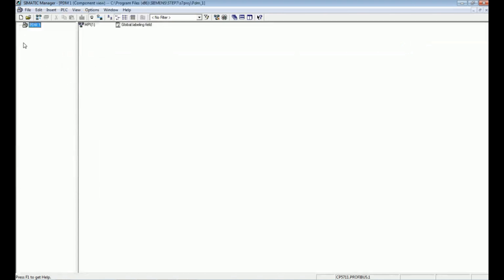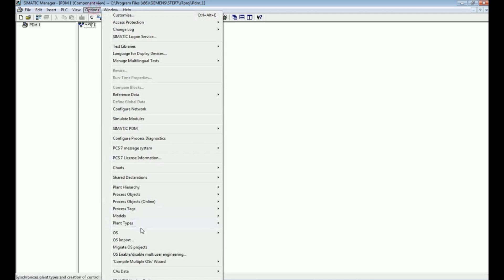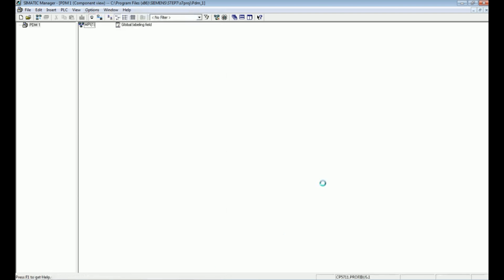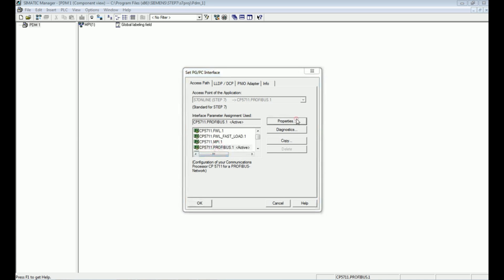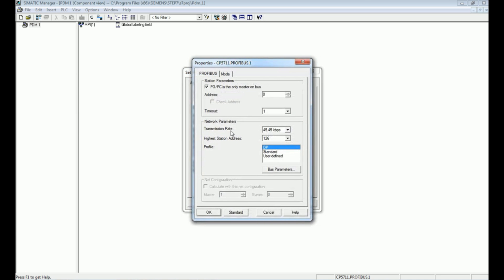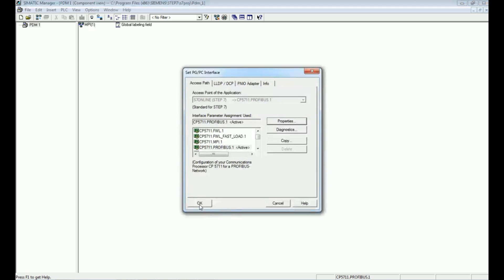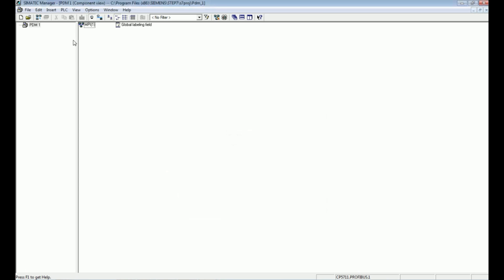After opening the project, we will first set the PG/PC interface to select the communication driver. Go to the Set PG/PC option and select the communication driver — CP5711 Profibus driver must be selected. The transmission rate must be set to 45.45 kbps. These are the changes we need to make first.